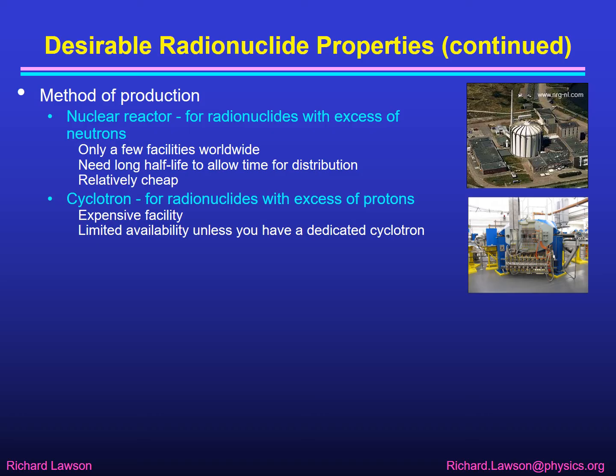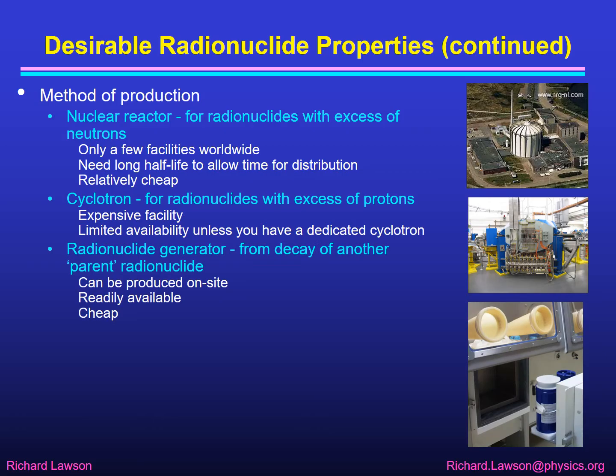Cyclotrons are used for radionuclides with an excess of protons, because the cyclotron can accelerate protons and let them hit targets of other stable nuclides to turn them into a radioactive nuclide with an excess of protons. These facilities are rather expensive and so if you're going to use a distant one it has limited availability unless you've got enough money to have a dedicated cyclotron on your own site. Radionuclide generators are useful where one nuclide decays into another — the parent decays into the one that we want — and these can be produced on site, are readily available, and are relatively cheap.